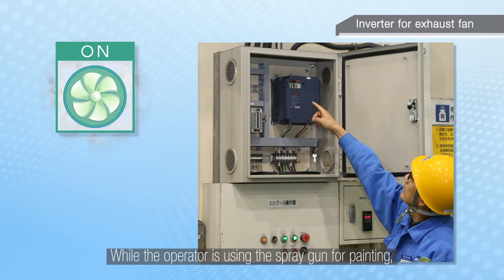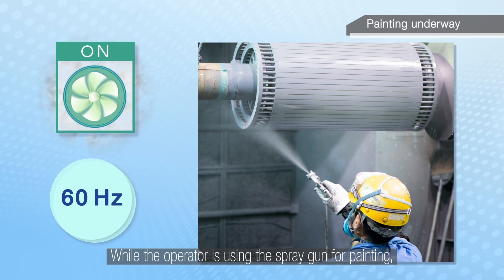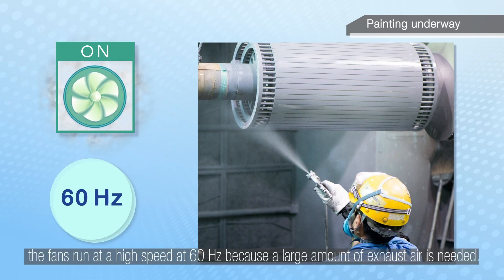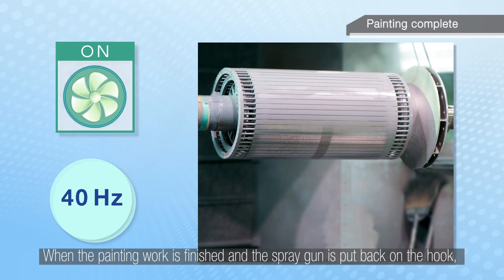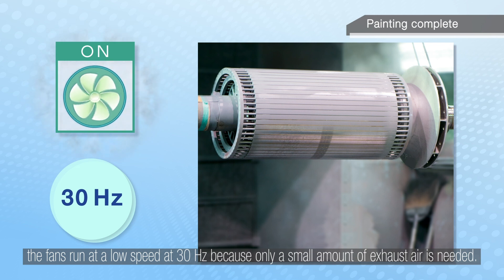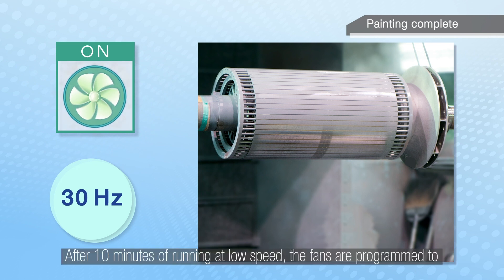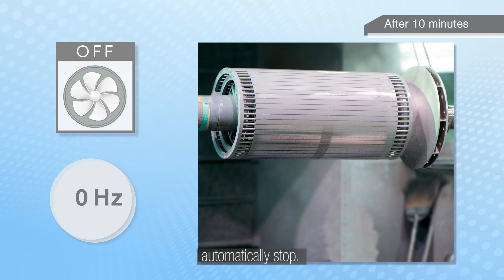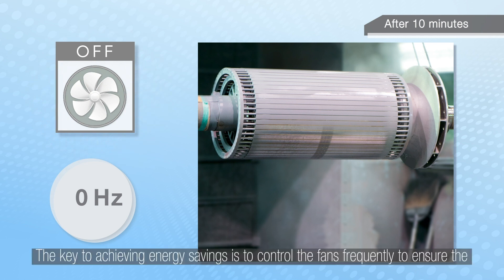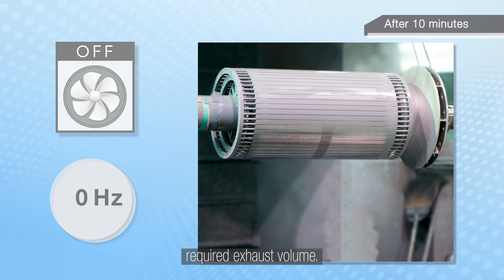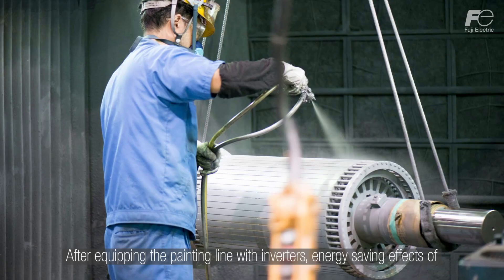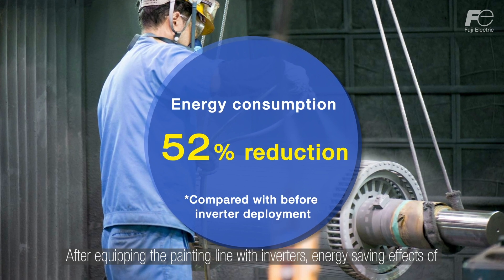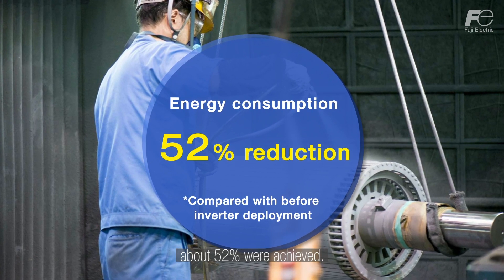While the operator is using the spray gun for painting, the fans run at high speed at 60 Hertz because a large amount of exhaust air is needed. When the painting work is finished and the spray gun is put back on the hook, the fans run at a low speed of 30 Hertz because only a small amount of exhaust air is needed. After 10 minutes of running at low speed, the fans are programmed to automatically stop. The key to achieving energy savings is to control the fan's frequency to ensure the required exhaust volume. After equipping the painting line with inverters, energy saving effects of about 52% were achieved.